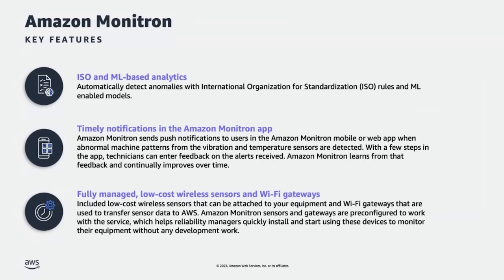The key features of Monitron are the ISO and ML analytics it provides. Monitron provides two types of analytics on the vibration data it collects: ISO and ML. ISO-based analytics are based on the ISO 20816 vibration standards. These standards determine the thresholds for different asset classes, applying broadly to four different classes of assets. Based on the threshold, Monitron notifies when an abnormal pattern is seen in the vibration parameters.